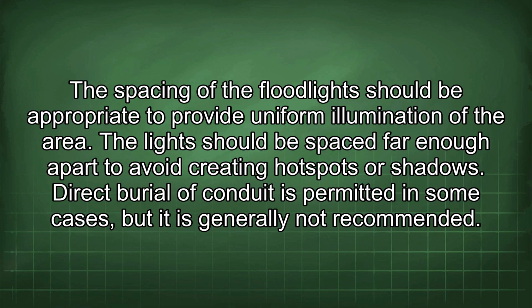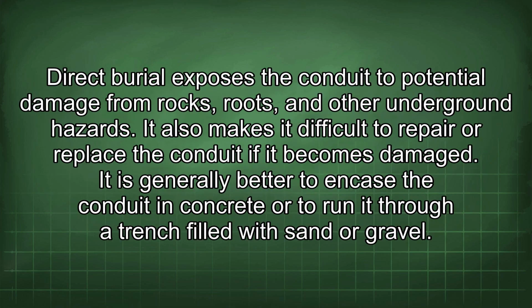Direct burial of conduit is permitted in some cases, but it is generally not recommended. Direct burial exposes the conduit to potential damage from rocks, roots, and other underground hazards. It also makes it difficult to repair or replace the conduit if it becomes damaged.